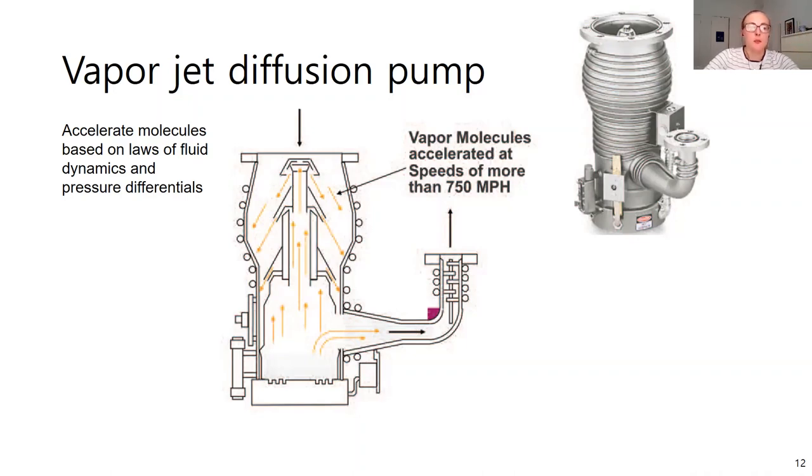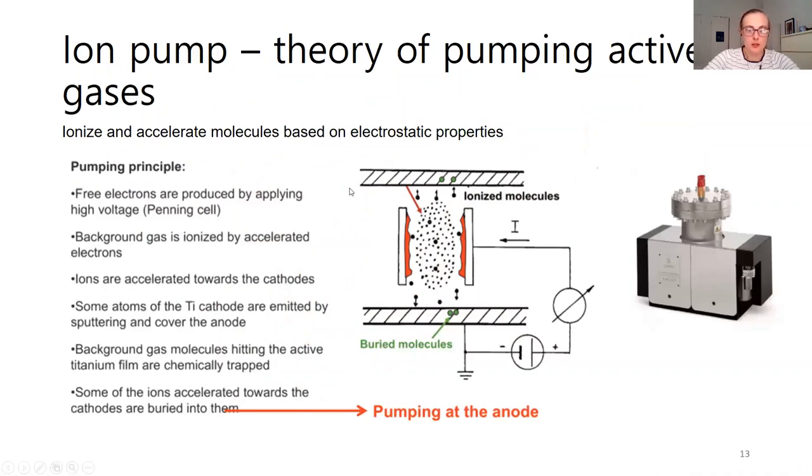You can also charge your molecules as well with an ion pump. Here's an example of this. You're going to ionize the gas that's in your system and then you are going to use some electrical charge differential and have a cathode or an anode where your ionized gas molecules will then absorb onto your cathode. So you're absorbing those gas molecules based on electrostatic interactions.